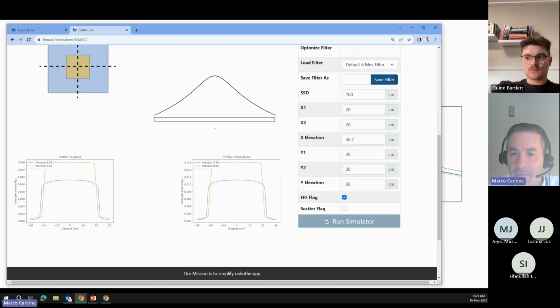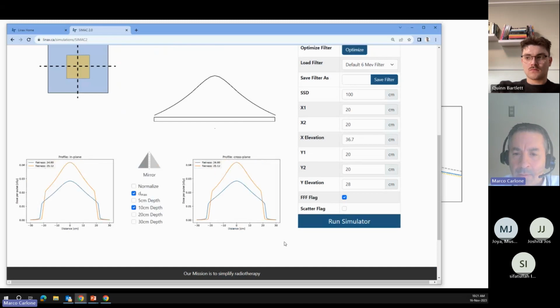Our simulator takes about 18 seconds to run, which is about 18 seconds longer than we want it to be, and we're working hard to improve that. The reason it takes so long is that it's really recalculating all the properties of the machine that create this beam, including the electron energy properties and then the photon beam properties. So that's finished now. So now we have our flattening filter free beam over here.